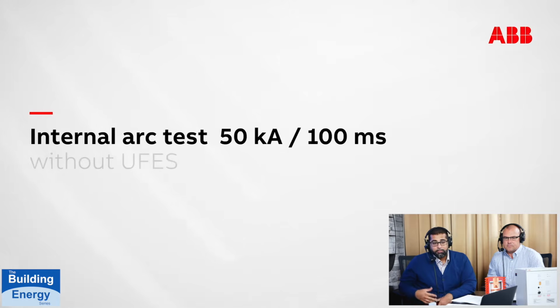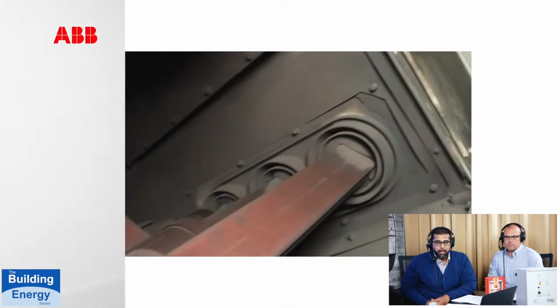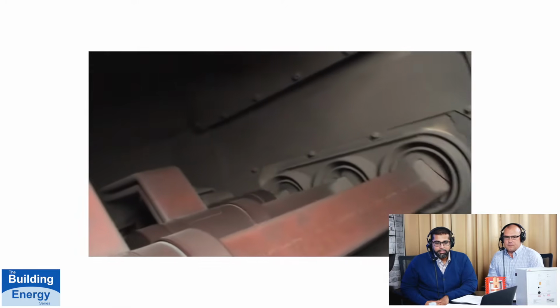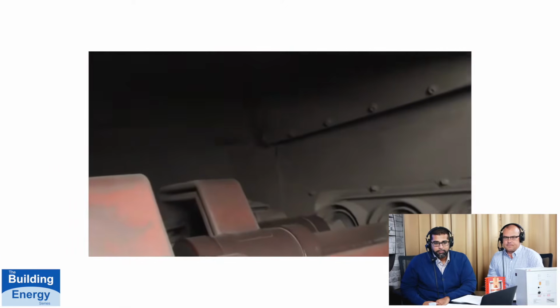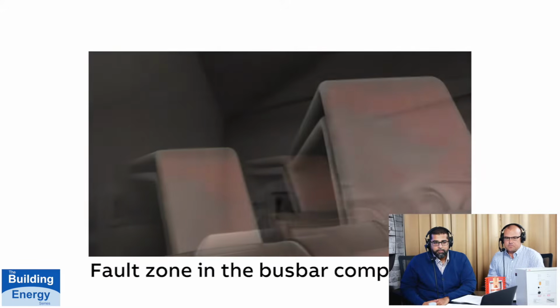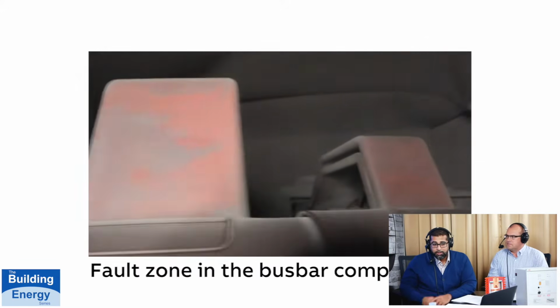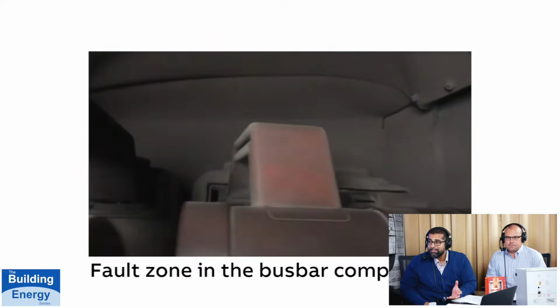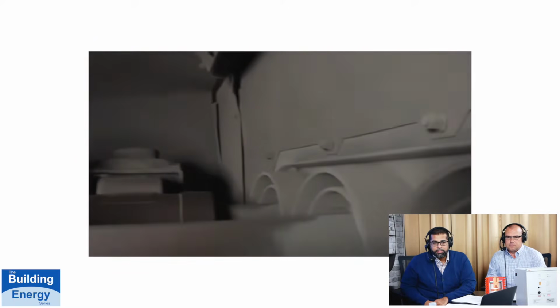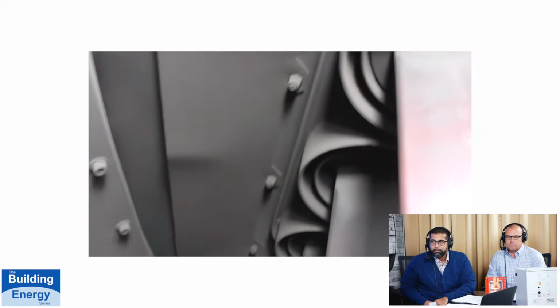So the first is the equipment without the UFES. Switchgear without UFES, and you'll see it doesn't look good. The amount of destruction that has taken place. You see there's a lot of carbon buildup, and this is just in a tenth of a second. For all intents and purposes, this gear is no longer usable.